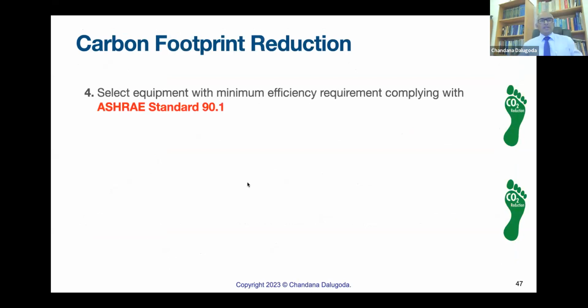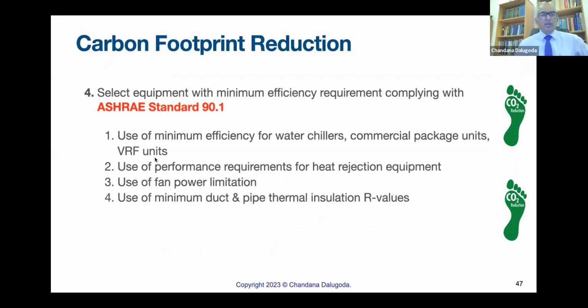Fourth item is to select equipment with minimum efficiency that we'll go through. Example, use of minimum efficiency for water chillers, commercial packages, VRF units, DX splits. Use of performance requirements for heat rejection equipment. What are the heat rejection equipments? Cooling towers. There's a cap. We can't just use cooling towers. Use of fan power limitation in air handling units and wherever.